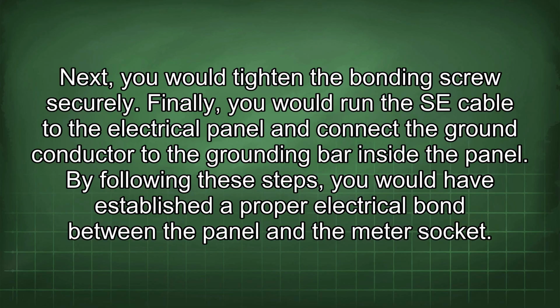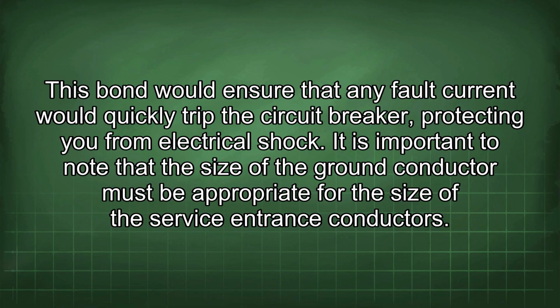Finally, you would run the SE cable to the electrical panel and connect the ground conductor to the grounding bar inside the panel. By following these steps, you would have established a proper electrical bond between the panel and the meter socket. This bond would ensure that any fault current would quickly trip the circuit breaker, protecting you from electrical shock.